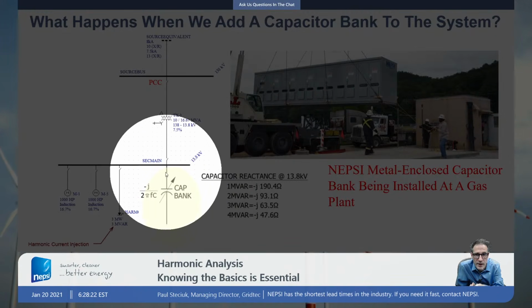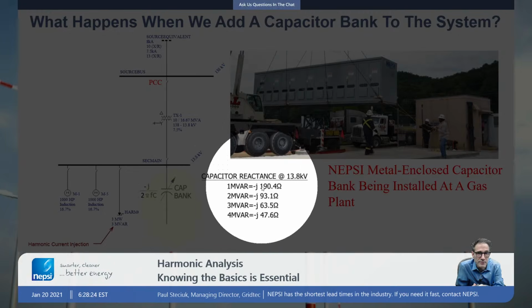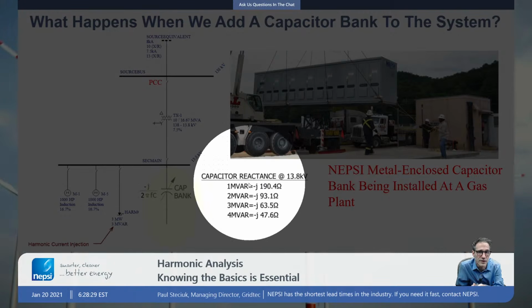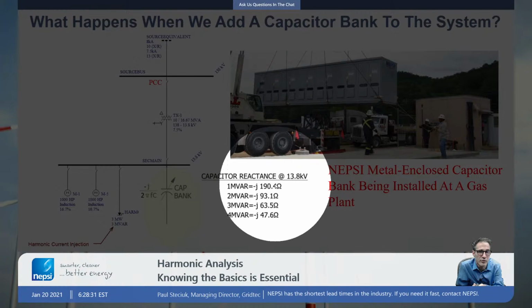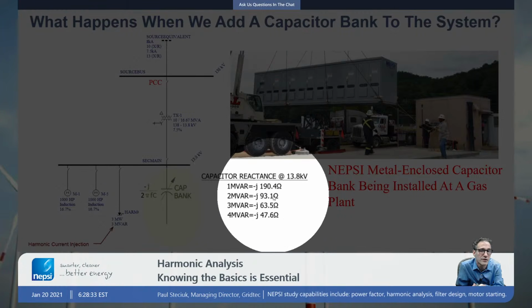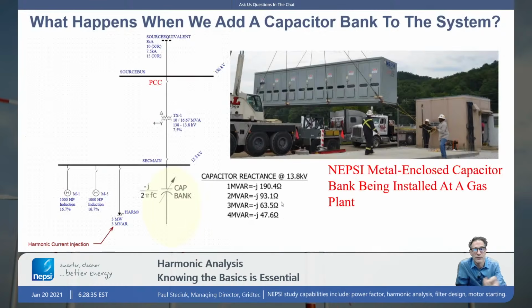We put that capacitor here in our model, and we can calculate the impedance of that capacitor at 50 hertz or at 60 hertz. So in this case, 1 megavar is 190.4 ohms, 2 megavars is 93.1, 3 is 63.5, 4 is 47.6. So as we're adding megavars, we're dropping down impedance. Makes sense. Megavars is equal to the voltage squared divided by X of C. So as we increase in megavars, we're dropping the value of X of C to increase in megavars.